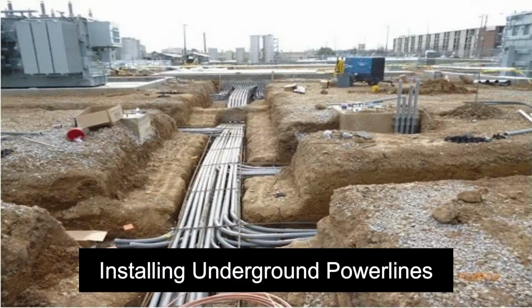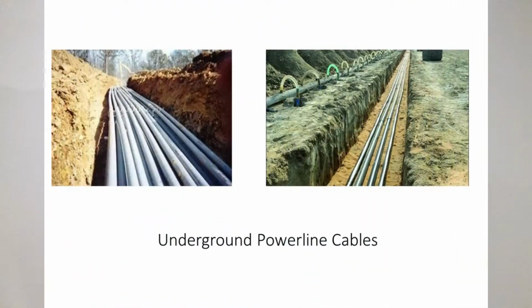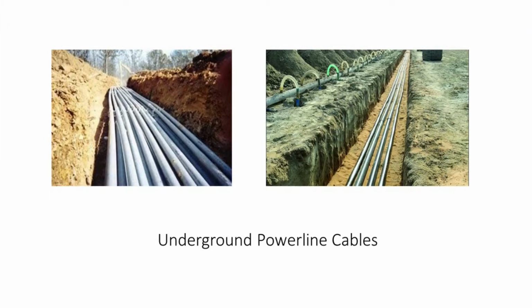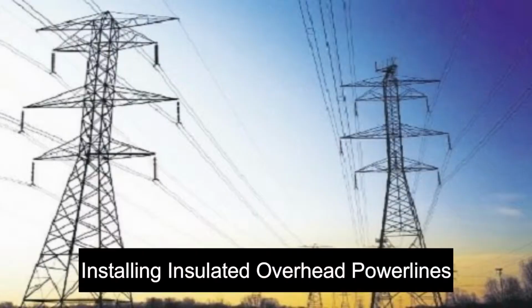The solutions for the reduction of bushfires are, first, installing underground power lines. This minimizes the risk of bushfire under extreme weather conditions like high wind speed or high temperature, as the conductors do not clash. This is installed only in the places where the weather conditions are high. Only phase-to-earth faults would be detected with an underground power line.